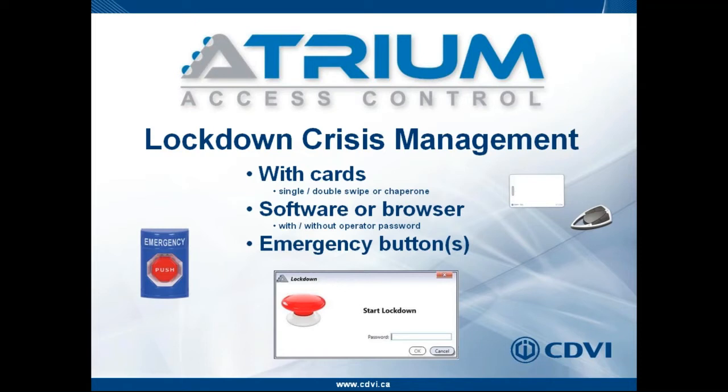We can initiate or trigger the lockdown with cards. If you're using cards or even transmitters, a wireless transmitter with a wireless receiver, you can have a double swipe of a card or a single swipe, and you can choose which cards can start the lockdown and which cards can stop the lockdown. You can also indicate that we will need two cards. So you have a single swipe or a double swipe to initiate lockdown, or you need to have two cards. So you need two people to start or stop the lockdown. And this can be individually configured.